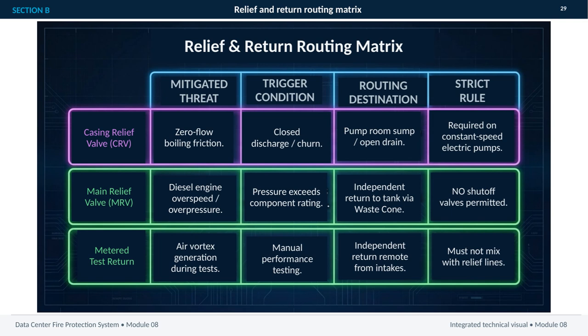For casing relief, the trigger is zero-flow boiling friction or closed discharge, also called churn. The flow routes to the pump room sump or an open drain, and this relief valve is required on constant speed electric pumps. The main relief valve addresses diesel engine overspeed, overpressure, or pressure that exceeds a component's rating. Its return must go independently back to the tank through the waste cone. Importantly, no shutoff valves are permitted in that path.